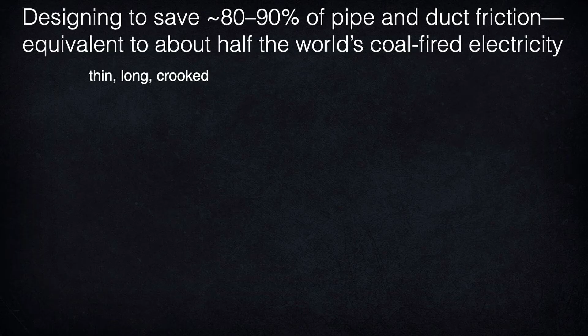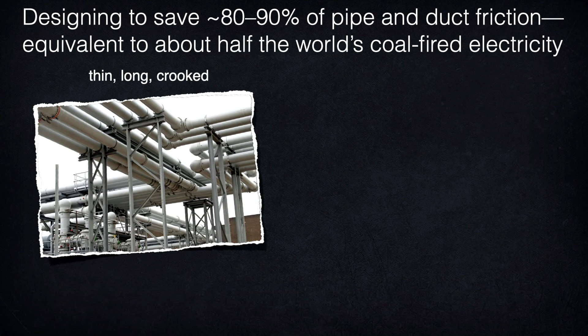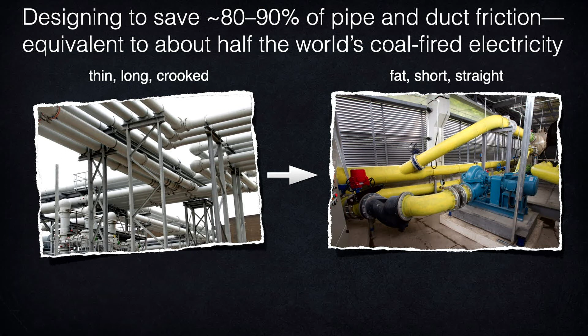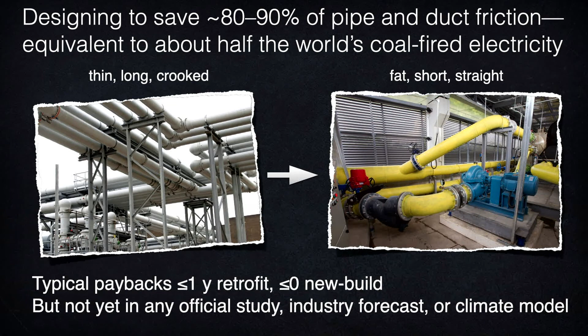In particular, better pipe and duct design just takes two changes in the design process. First, we specify big pipes and small pumps, not small pipes and big pumps. You see, the friction in a pipe falls as nearly the fifth power of its diameter. So how fat should the pipe be to optimize the friction? Well, the textbooks say to make the pipe just as fat as will repay its extra cost over the years from the saved pumping energy.